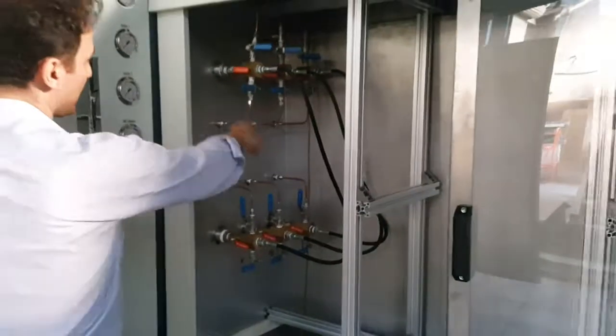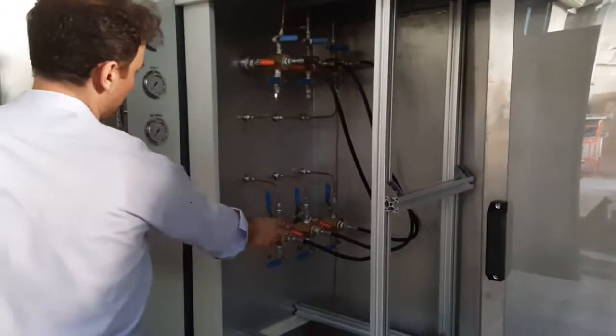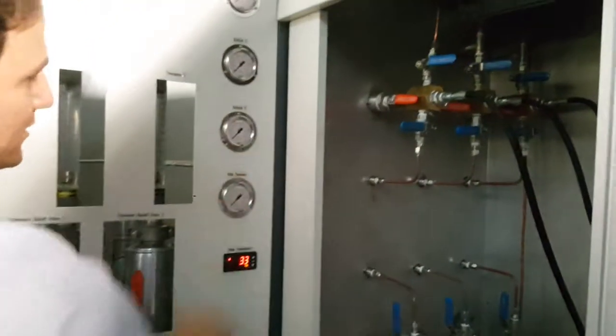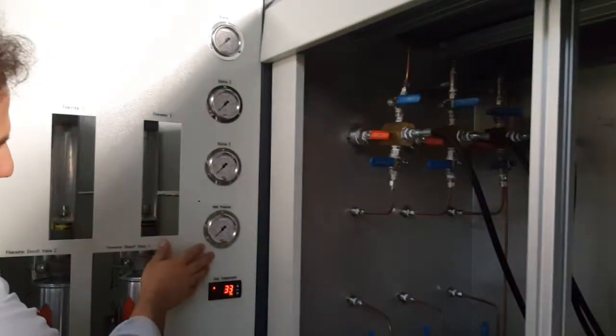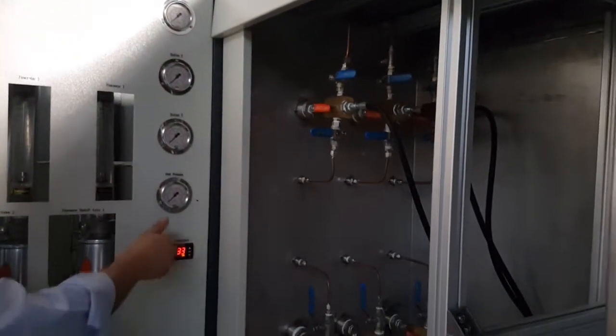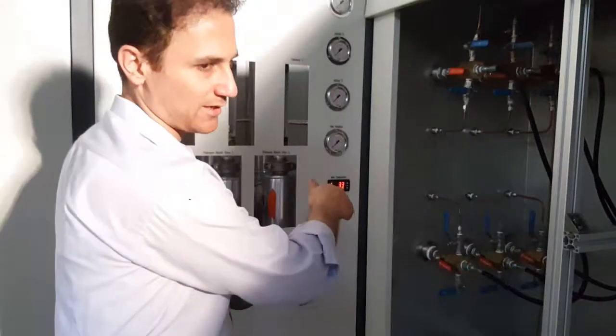We have valves to attach the recirculation pressure to dial gauges, a mainline inlet pressure gauge, and an inlet temperature digital display. At first look, an operator can know which cycle the machine is working in.